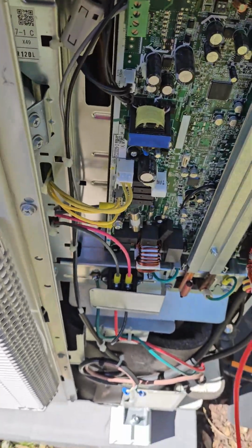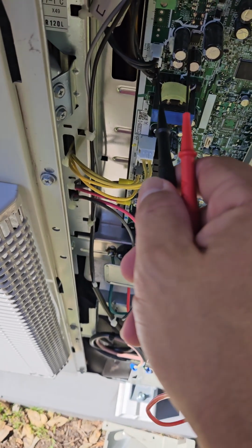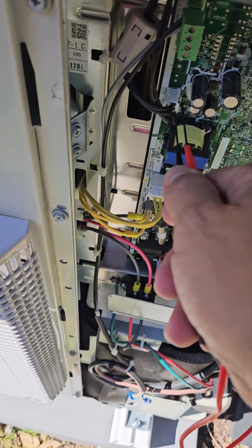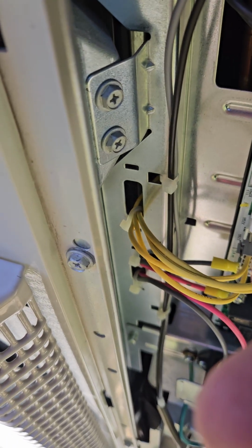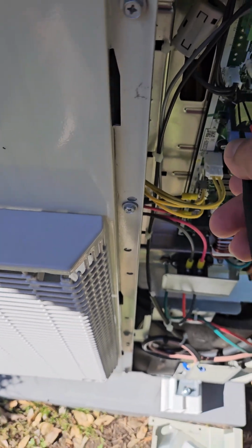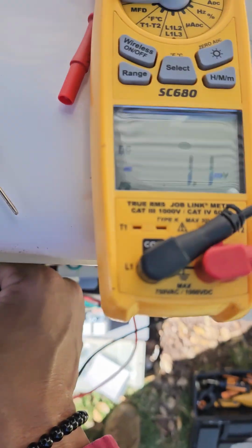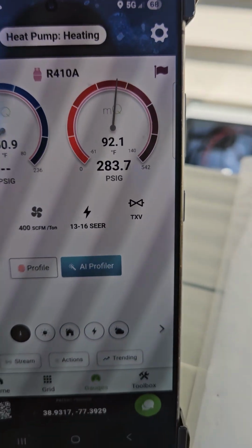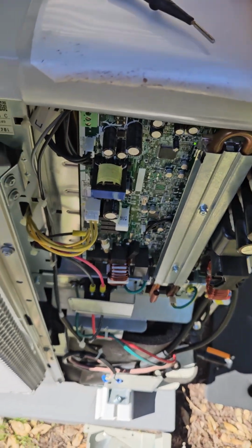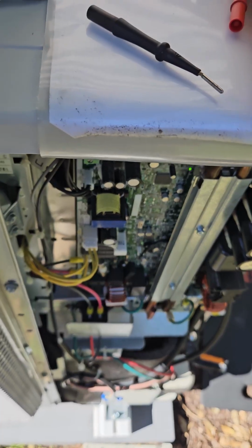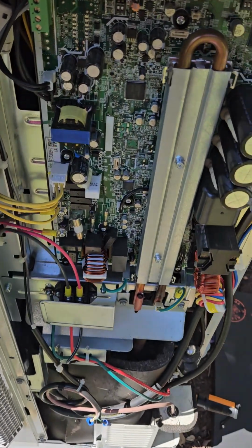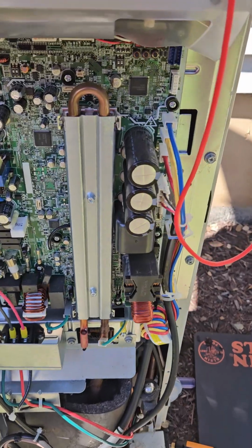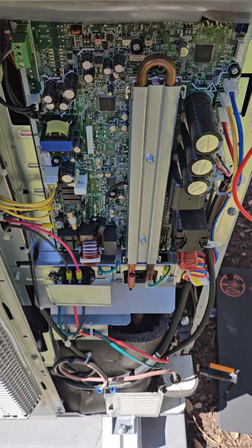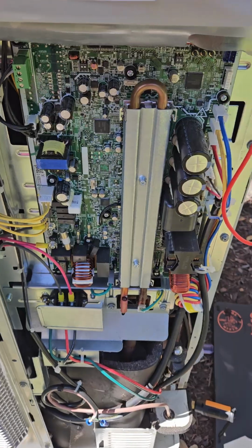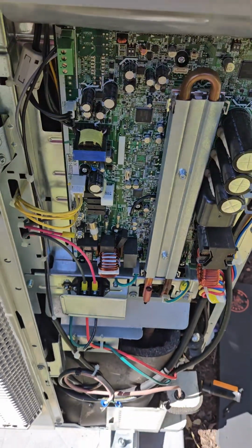Now the way I test it now is the high pressure sensor right here is supposed to be reading less than 2 DC volts, so that means it's under 200 PSI or close to, less than 300 PSI. So we have 1.1 volts. That means 283 PSI. So as far as the pressure, the system is not overcharged, and we don't see any restrictions so far. The system has been running for about 5 minutes. So I'm going to let it run a little bit longer, and then I'm going to run a system test and see if there are any other error messages regarding the code 13.